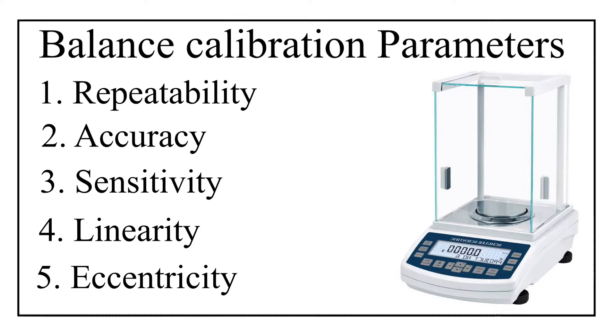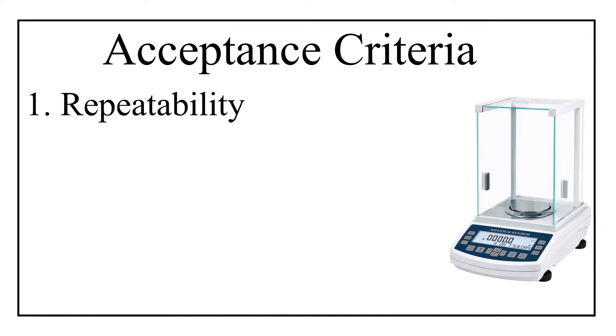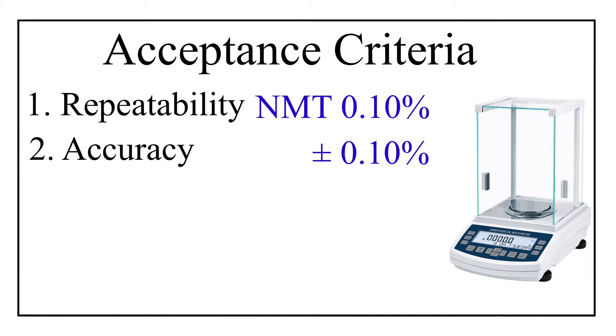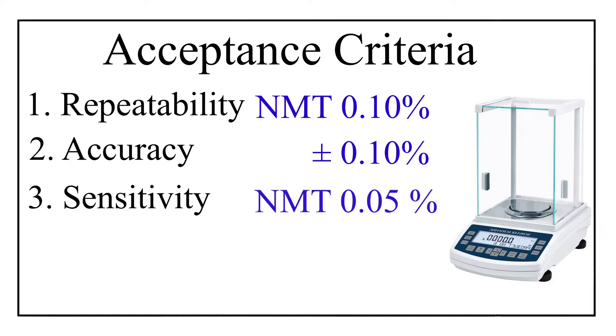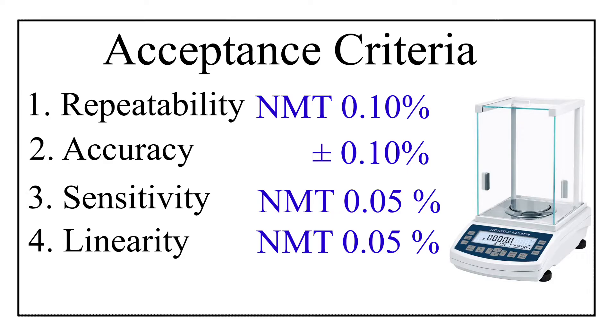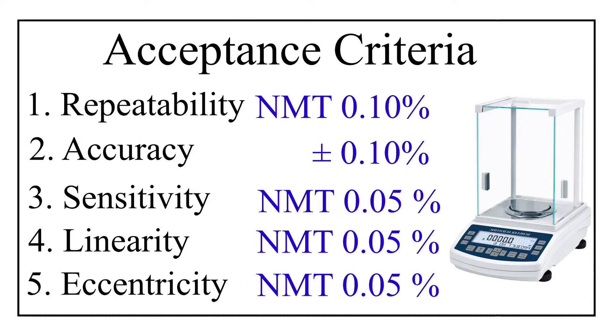Now comes the acceptance criteria for each parameter. First, repeatability: the acceptance criteria is not more than 0.10%. Then accuracy: the acceptance criteria is plus or minus 0.10%. Then sensitivity: not more than 0.05%. Then linearity: not more than 0.05%. And finally, eccentricity: not more than 0.05%.